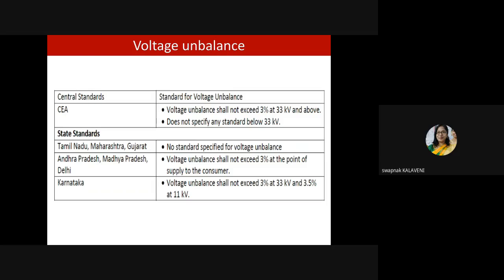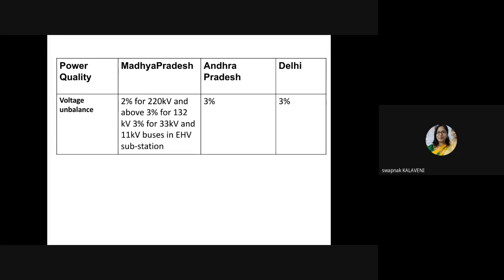Now we are thinking about the voltage unbalance permitted between the three different phases. As per the Central Electricity Authority, voltage unbalance should not exceed 3% at 33 kV and above. So the allowed unbalance is only 3%. It should not go beyond 3%. This is the standard fixed by the CEA, the Central Electricity Authority. Say, for example, think about Madhya Pradesh. Their variation is 2% for 220 kV and 3% for 132 kV. It means their regulation is slightly better than the Central Electricity Authority, which fixed 3% unbalance. But here it is 2% for 220 kV and 3% for 132 kV.